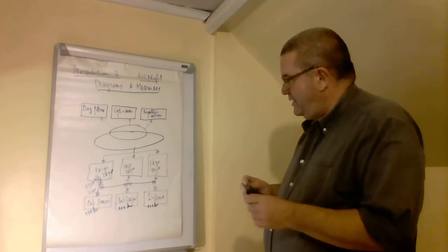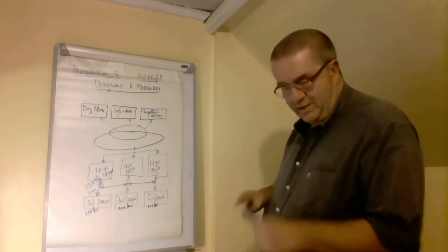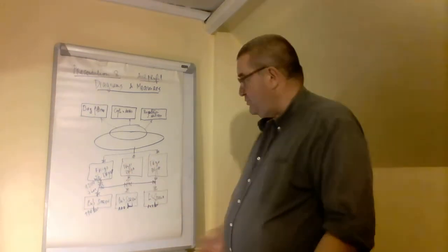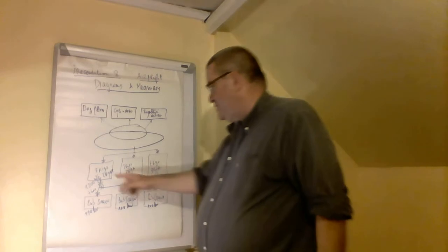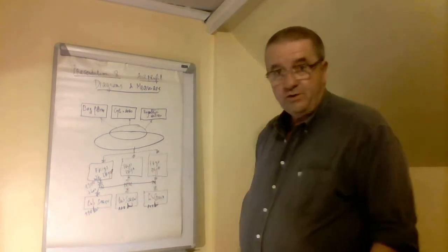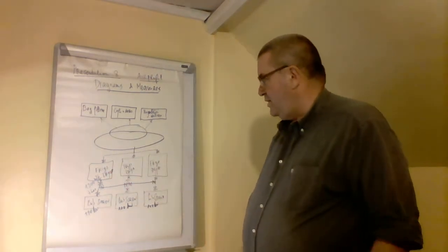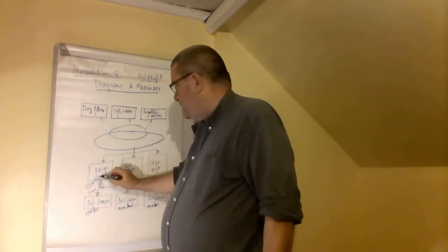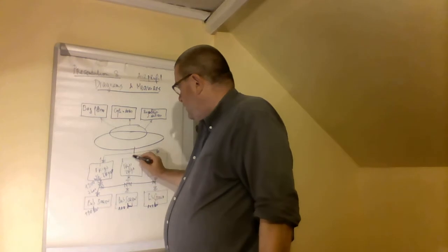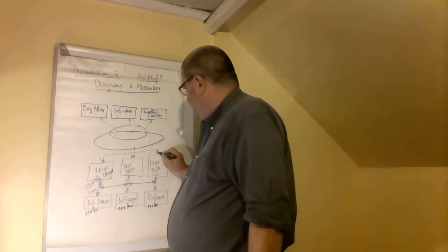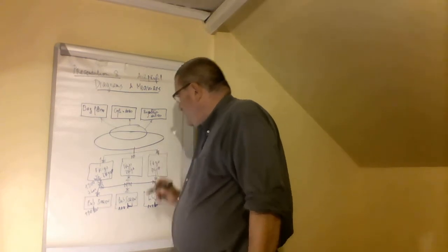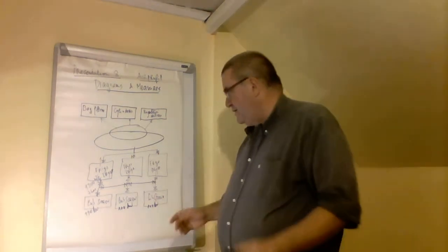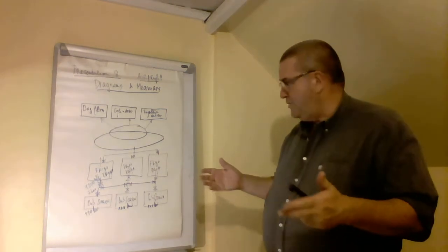Very often, the two dryers are not exactly the same. Maybe they're not at all the same dryers. You have taken this dryer from another plant, where it was not used any longer. So there is a risk that more air goes through a big dryer, and only a small amount here and a very small amount here. So you are never quite sure how the air will choose to go.